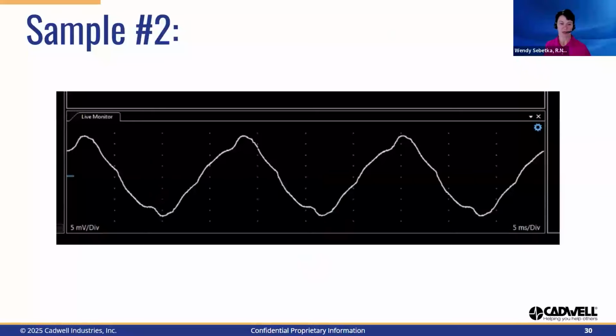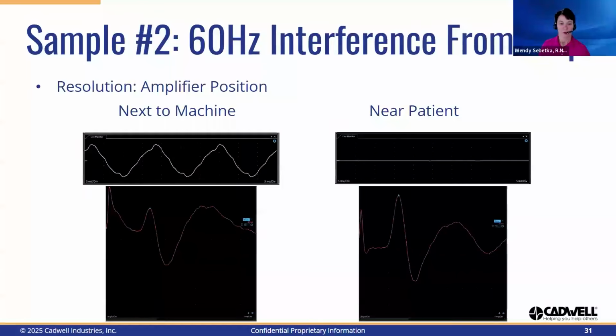Key points of sample number 2: it doesn't show any spiky, disorganized waveforms, but it does look very consistent and sinusoidal in appearance. These details lead me to suspect a non-physiological source. The recommendation was made to extend the amplifier away from the machine and closer to the patient. The artifact was eliminated and a cleaner response with a more defined onset was able to be obtained.